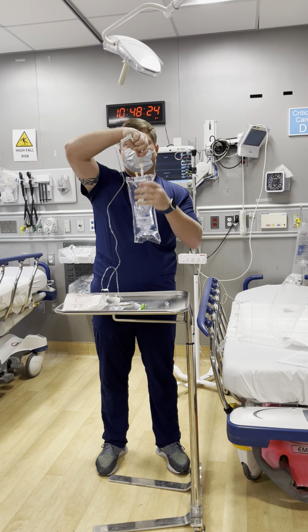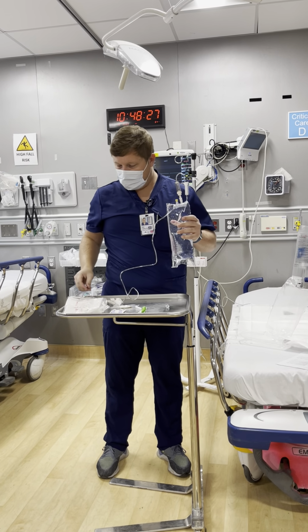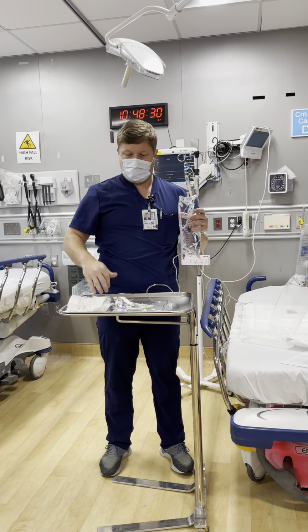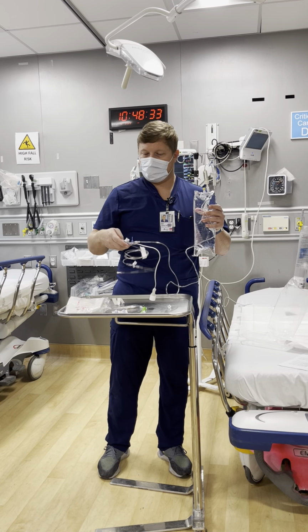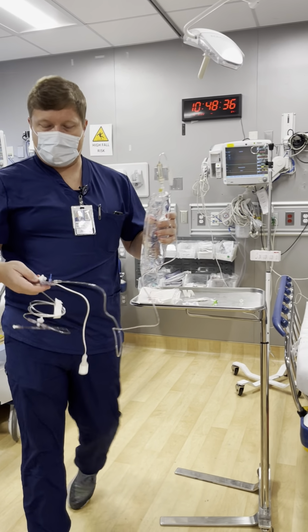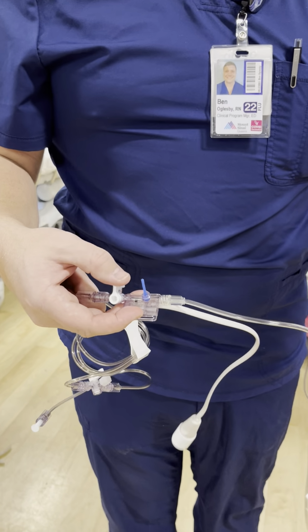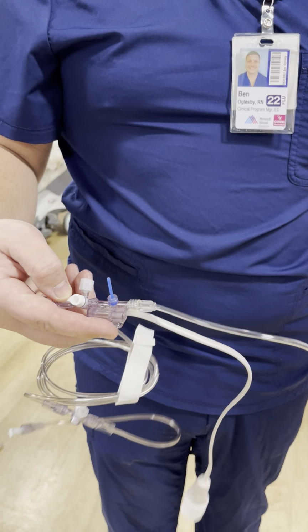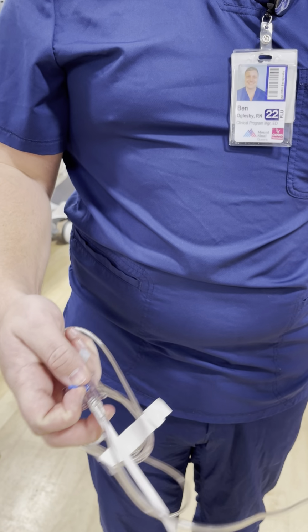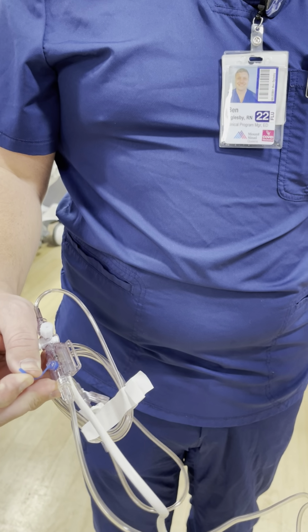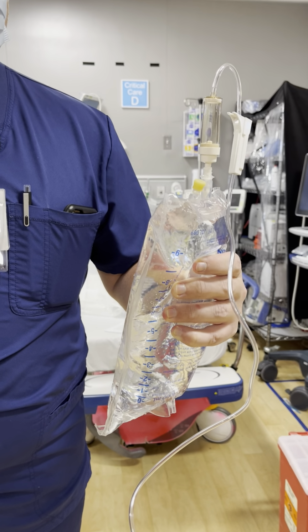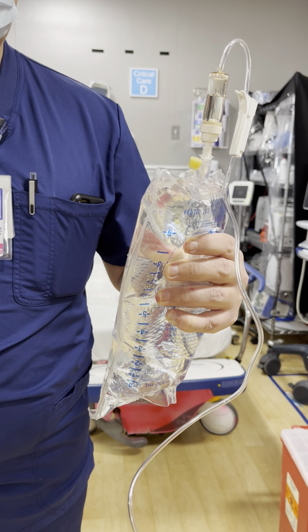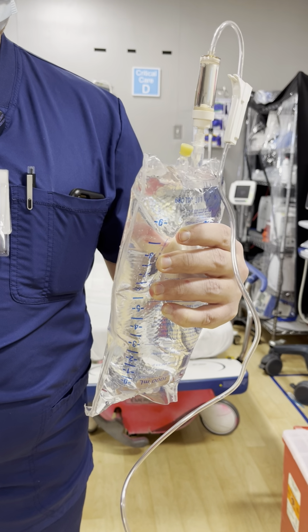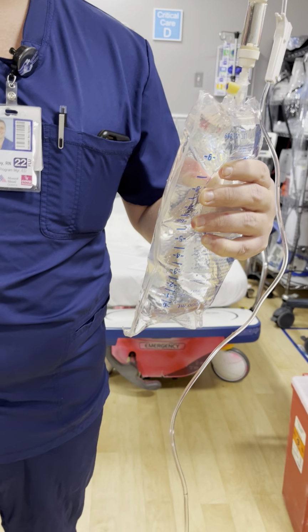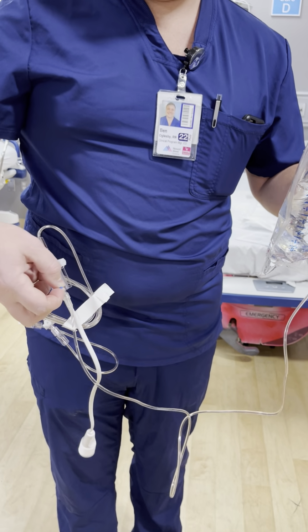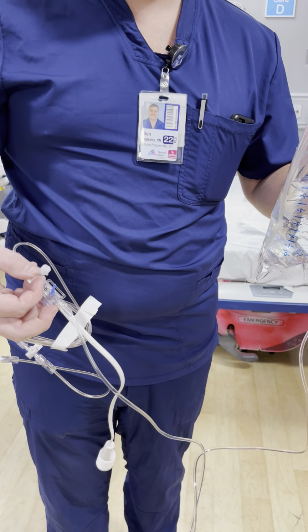and then re-spike. Okay, so with that, you want to remain holding it up, and when you get to the end over here, you're going to want to flip your stopcocks, and the first stopcock you come to will be right past the transducer. You're going to flip it off to the patient, which is away from the bag, and then you're going to pull this little blue tab right here. That allows all the air to be expressed and fluid to flow through the line. So we will start filling it up. Be careful not to get air bubbles all in your system, and continue to express it until fluid flows out there. And then once you're finished, you can actually release the blue tab.